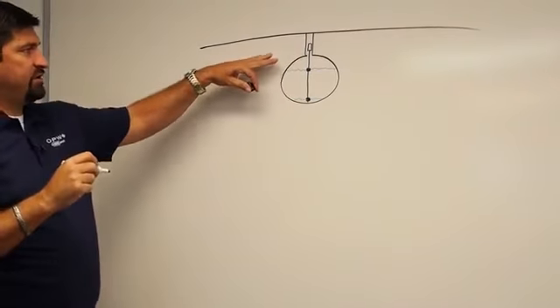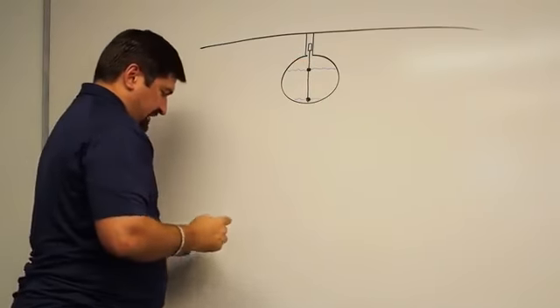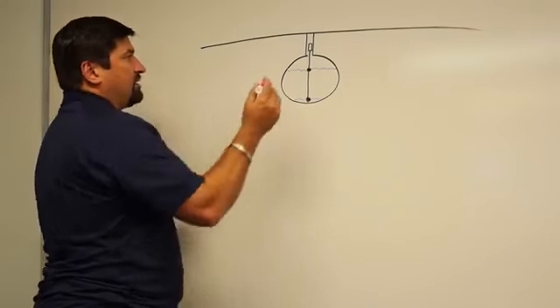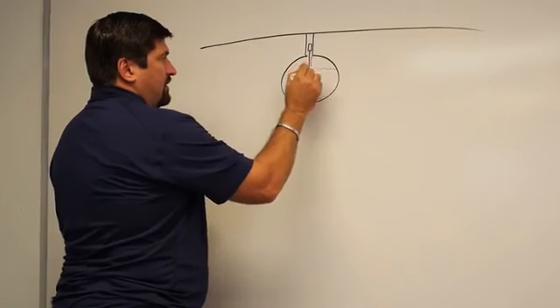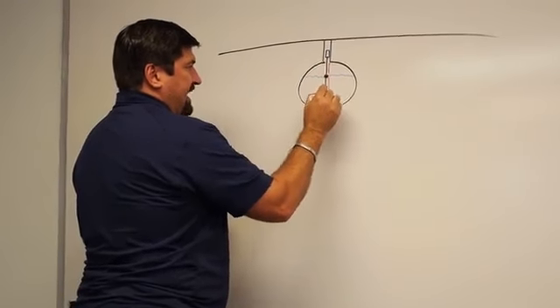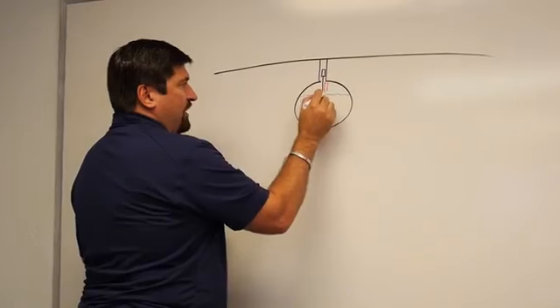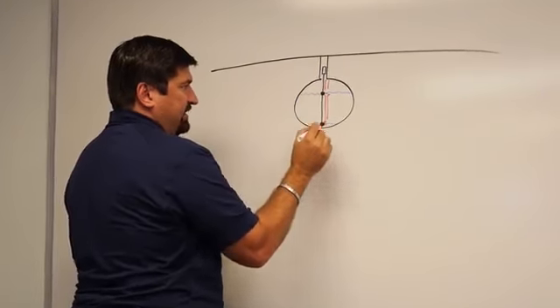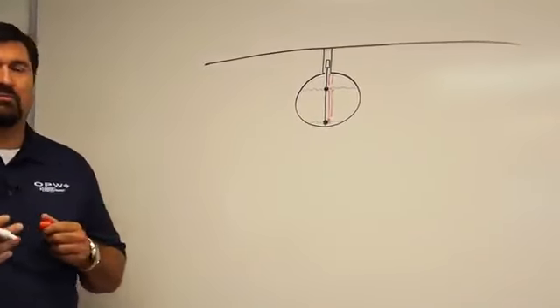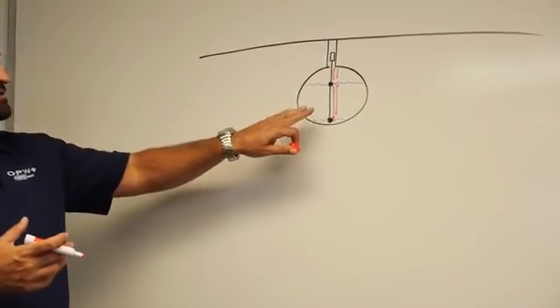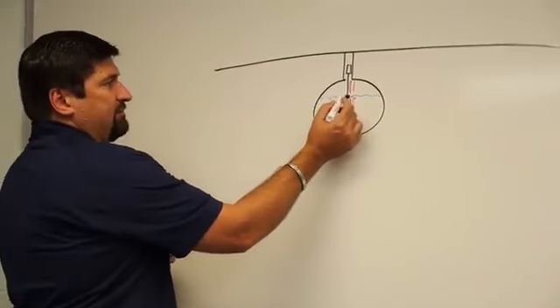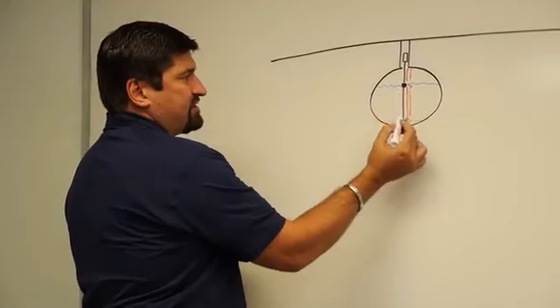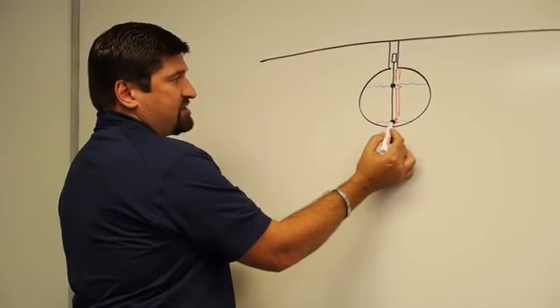And basically what you're doing is sending a pulse down this probe, and then it gets reflected back up to the head, and wherever these floats are, you get a little bitty spike on a waveguide called a magnetostrictive probe. So what's happening is that I'm very accurately measuring where this float is on the surface of the product and where it's at on the surface of the water.